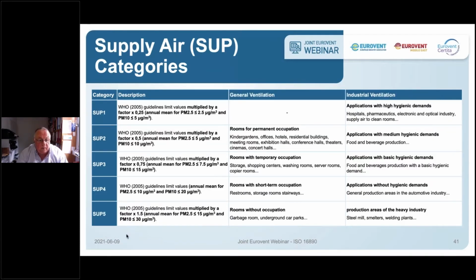On the next slide, we have to choose the desired supply air quality. Supply air, that's the air that's going into the building. Maybe let's start here with supply air quality 4. These are exactly the limit values of the WHO guideline, and in the second column, these are rooms in the field of general ventilation: restrooms, storage rooms, stairways. In an industrial environment, the supply air here is for general production areas in automotive industry, for example. These are applications without hygienic demands.